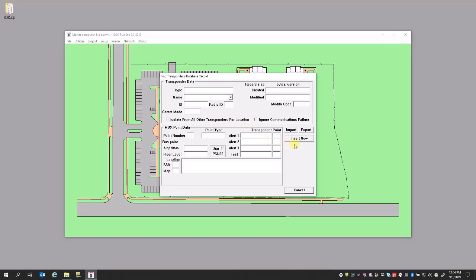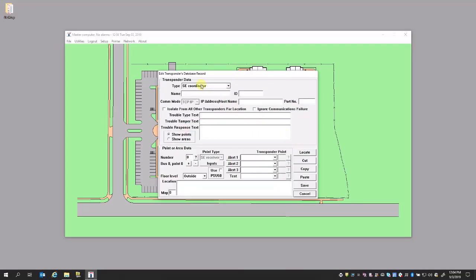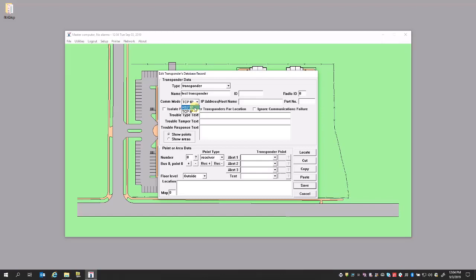We're going to start with inserting a new transponder. Select transponder, give it a name. Your form of communication is either TCP or RS-232. If you're using TCP, that means you're using a serial to ethernet connector at the transponder. For this case, we're going to use RS-232. Comport Index A was described in a previous video illustrating what Comport Index A is and how that's assigned to a Comport.